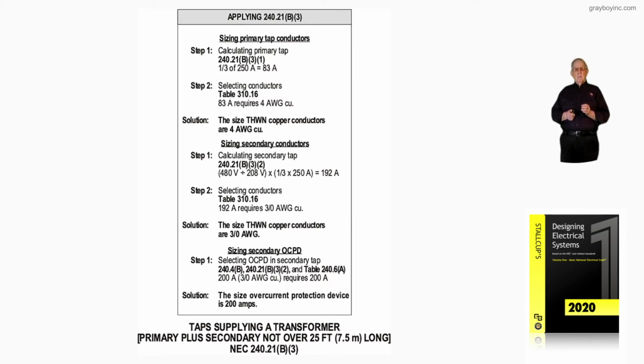Now, moving to the secondary side of the transformer, now we're looking at 240.21(B)(3) item 2. So we take 480 divided by 208 times 1/3 times 250, and we come up with 192 amps. The size of the conductor for the secondary tap has to be at least 192, so we're using a 3/0 for 200 amps, which will take care of the 192.